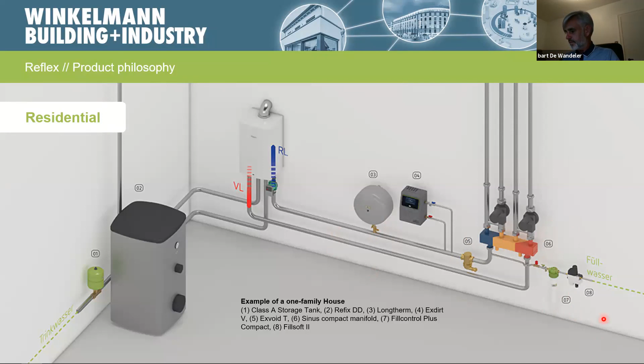And if we have a big pressure drop, the Servitec can also maintain that pressure drop, and make sure we have a small water makeup so the water reserve in your static vessel is also protected. We also provide manifolds for systems, and a big part of Reflex is the water quality, which is quite important today because we are working with small boilers, small pumps, small heat exchangers. The advantage is that we don't have to add any chemicals to a closed water system.